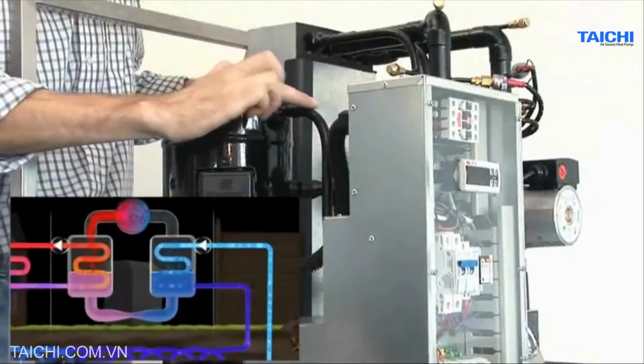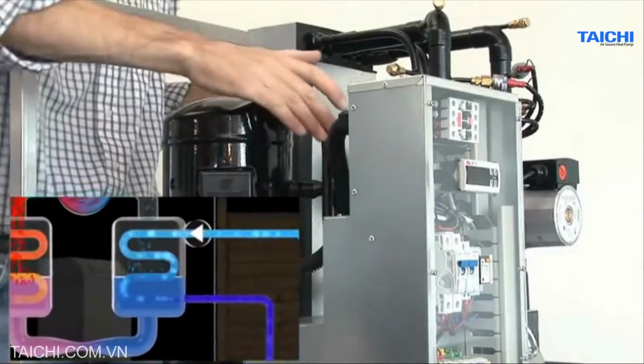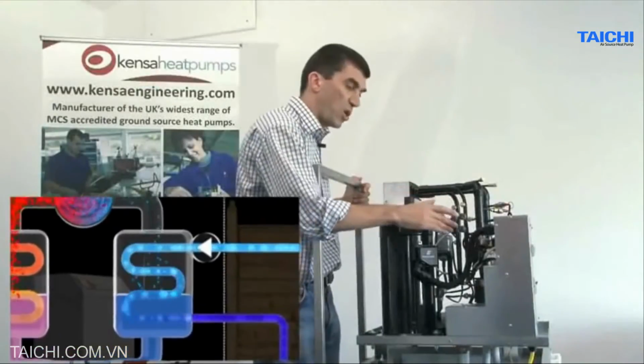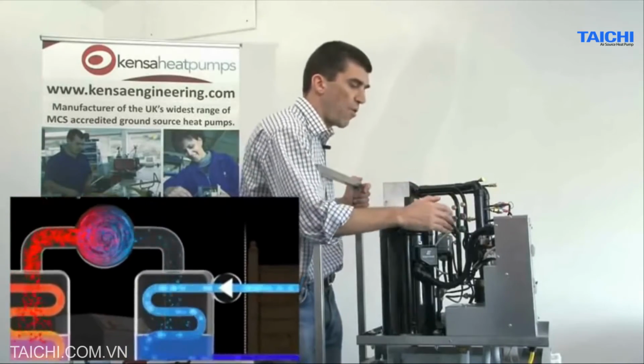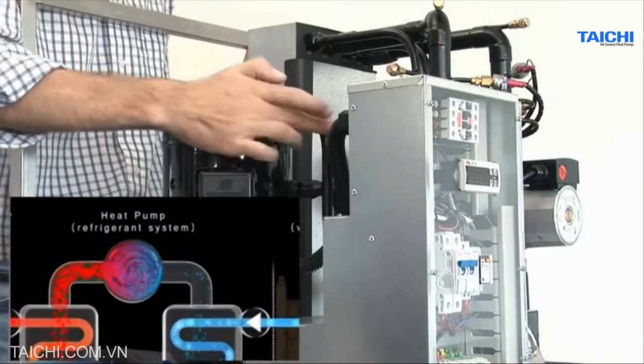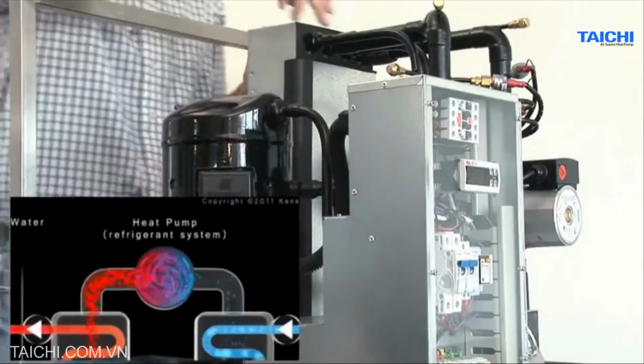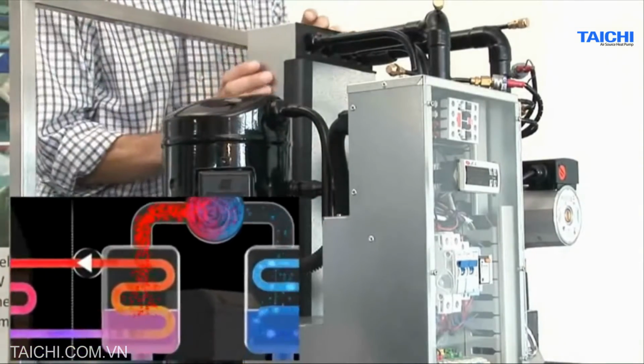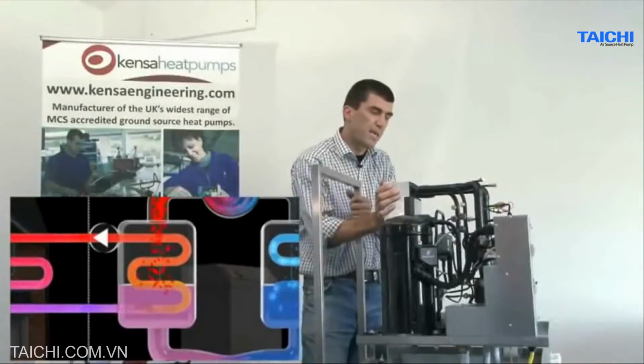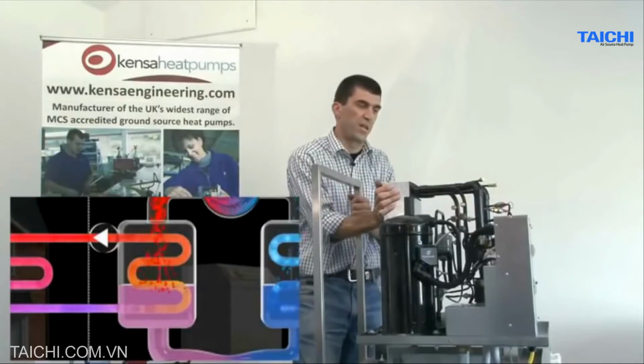So the gas in vapor form containing our heat energy, and I'll come back to why it's got the heat energy at the other end of the story, is discharged from the discharge pipe of the compressor and flows into our condenser heat exchanger. On a Kensa heat pump, that's always the left-hand heat exchangers.